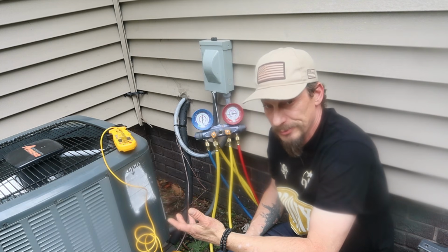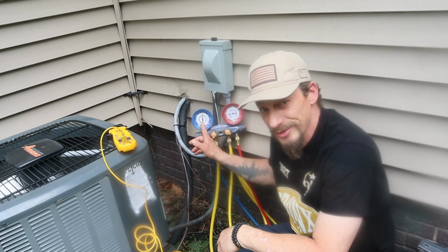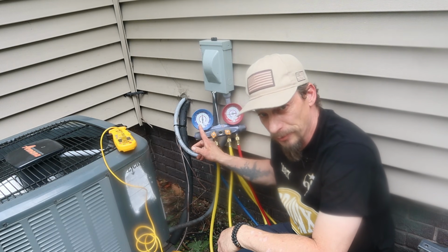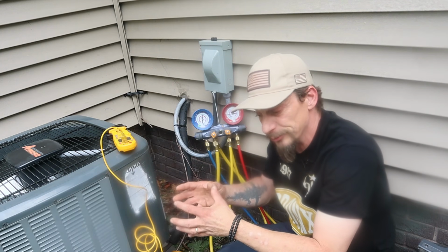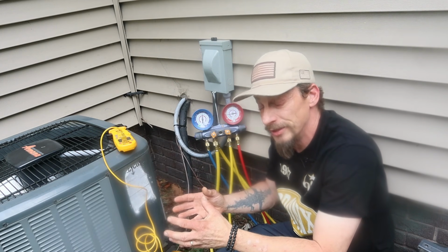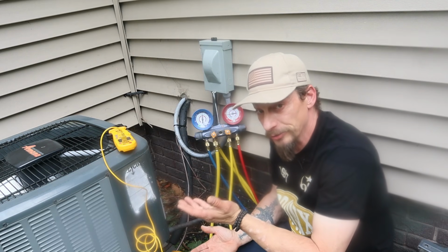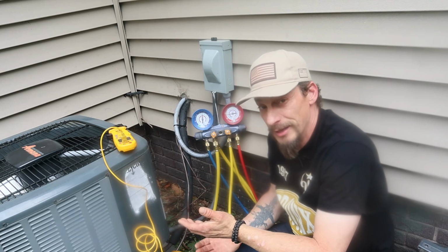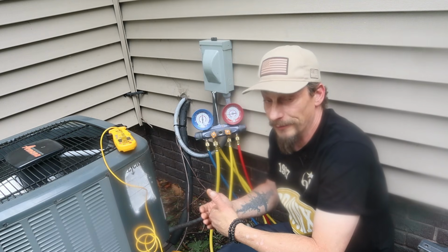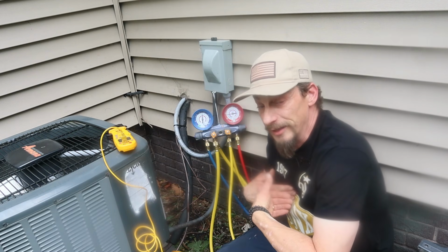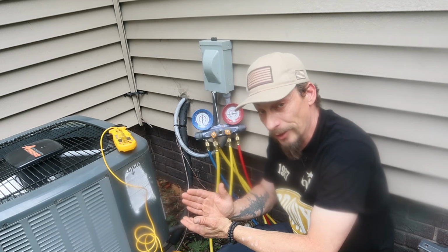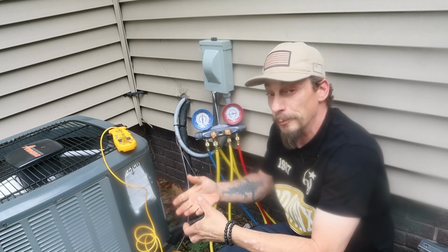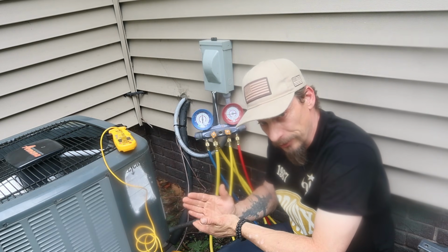Now, while that process was occurring, we also saw a slight increase in the suction pressure. And what was happening there was because all that refrigerant was retaining a lot of heat at first, that created a greater pressure differential across the metering device. And so what that did was force the metering device open a little more, feeding more refrigerant into the evaporator coil, and that's the pressure increase we saw. With more refrigerant, we can absorb more heat, and the pressure started to increase a little bit.